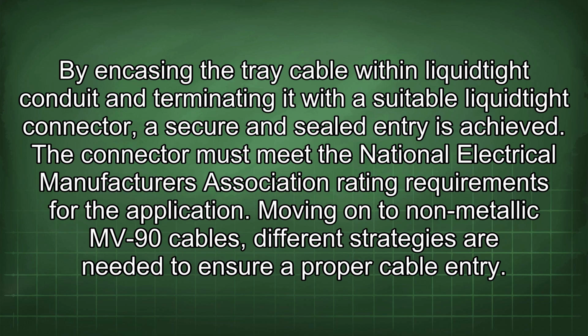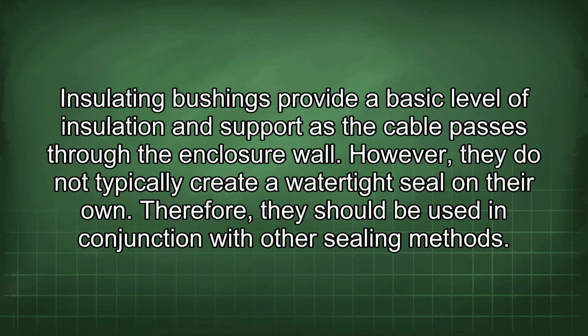Moving on to non-metallic MV-90 cables, different strategies are needed to ensure a proper cable entry. Insulating bushings provide a basic level of insulation and support as the cable passes through the enclosure wall.